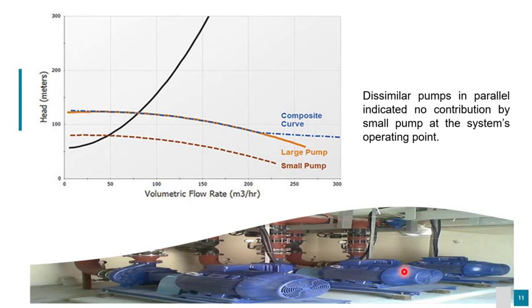This slide for dissimilar pumps in parallel indicates no contribution by the small pump at the system's operating point. So with the small pump and the large pump, there is no contribution by the small pump at the system operating point.